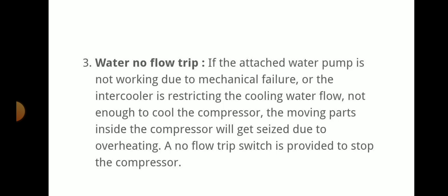Water no flow trip means if the attached water pump is not working due to mechanical failure, or the intercooler is restricting the cooling water flow and it is not enough to cool the compressor, the moving parts inside the compressor will get seized due to overheating. So a no flow trip switch is provided to stop the compressor.